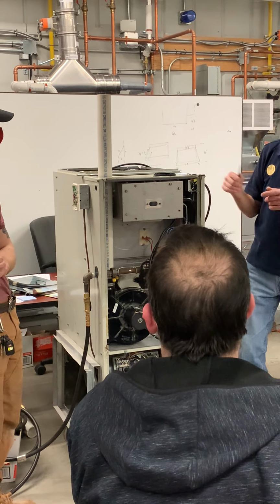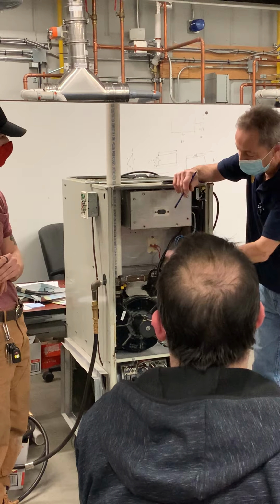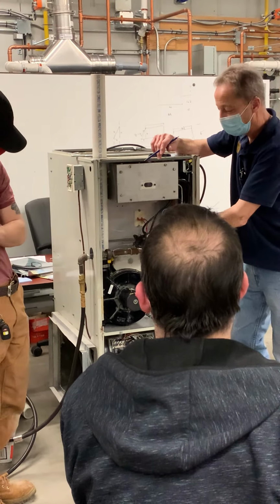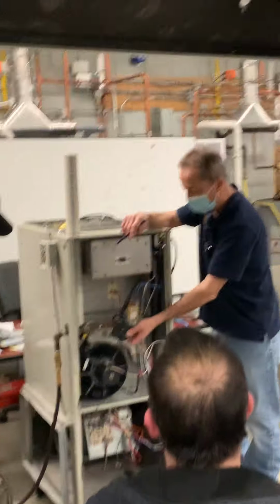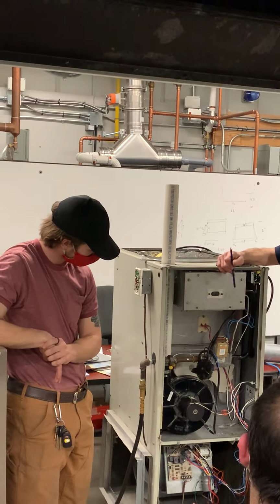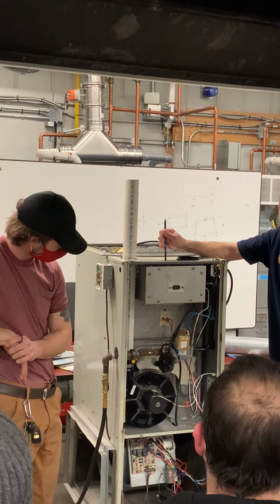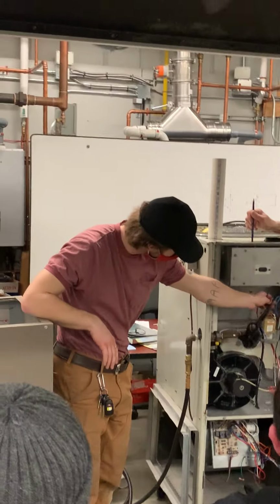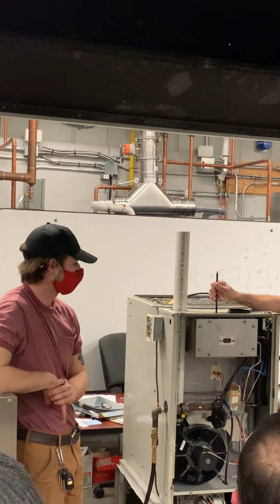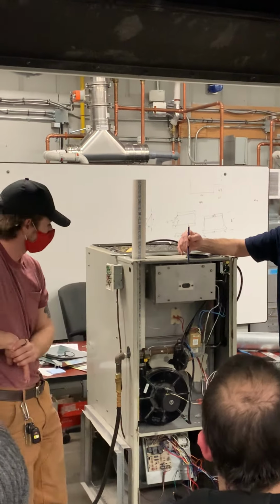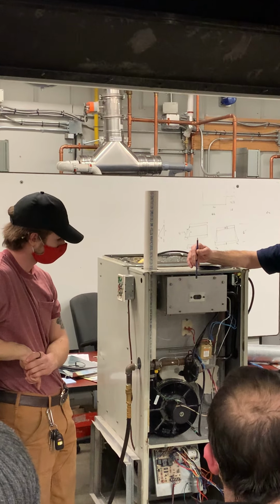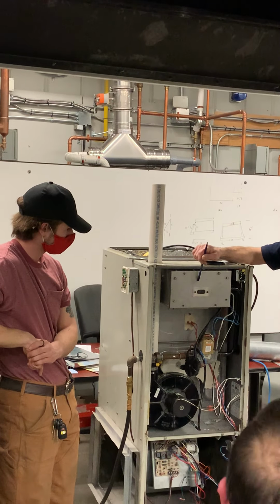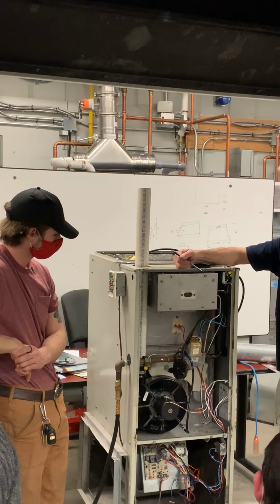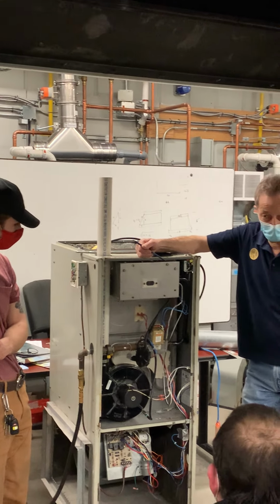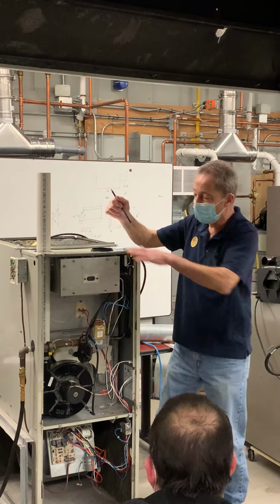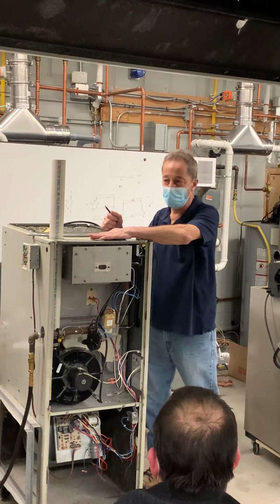Got a question for you though. I'm looking at this, why are there two hoses on the pressure switch? Can you give me any legitimate reason for that? To make sure there is a pressure differential. Okay, so it's sensing a pressure differential between... which pressure has to be more negative, the burner box or the inducer? Probably the inducer. You're correct. If I block the intake, what happens to the pressures?